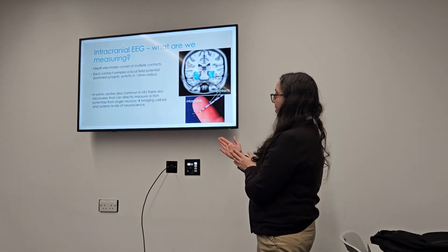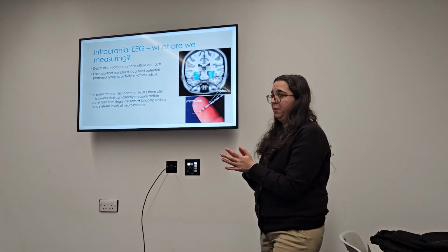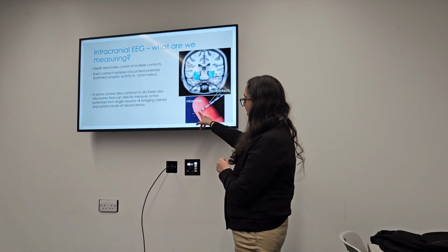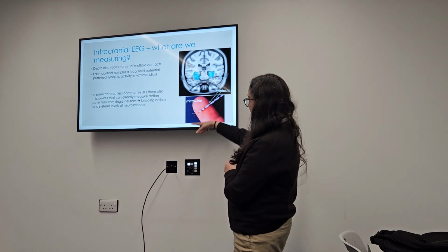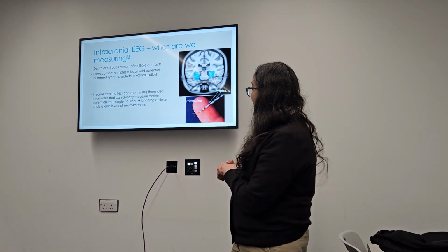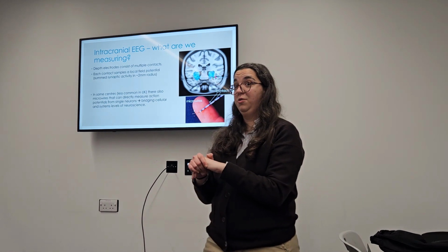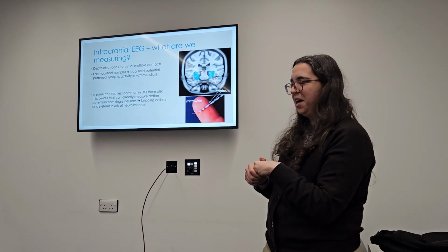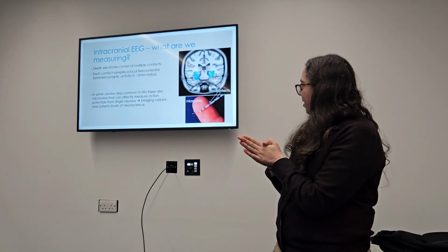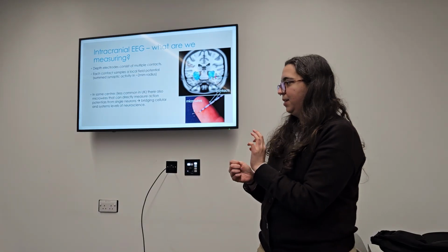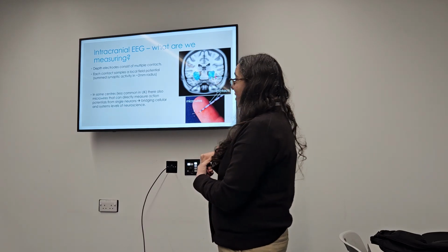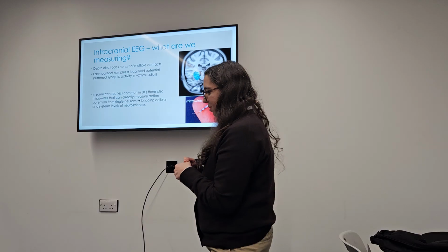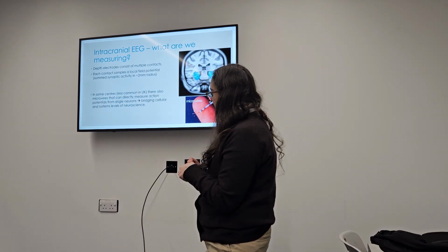So in some centers, although again, less common in the UK because this is purely for research purposes, it serves no clinical meaning, the electrodes will have microwires. These are the tiny hairs at the end of the electrode that are able to pick up action potentials from a single neuron or multiple unit activity from a number of neurons. That's much more common in continental Europe and in the US. In the UK, I think, if I'm not mistaken, it's still not been approved for use, although there have been conversations about making this available in the near future.